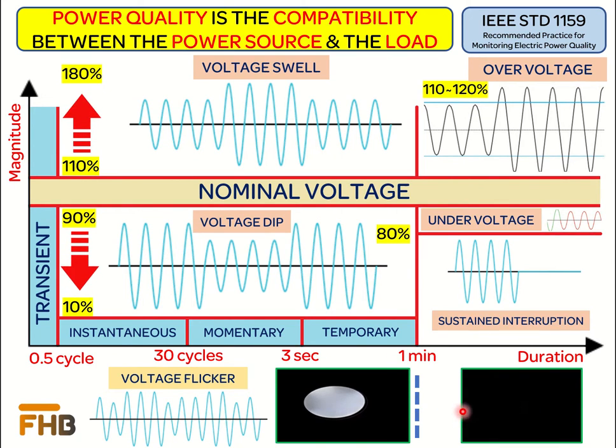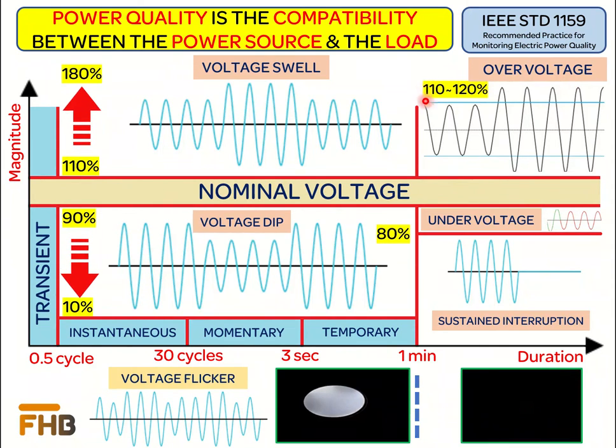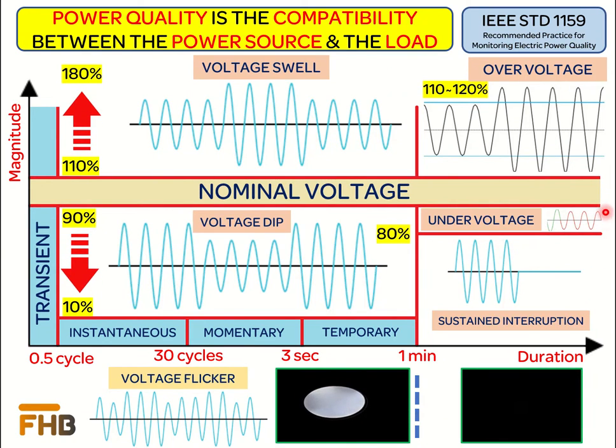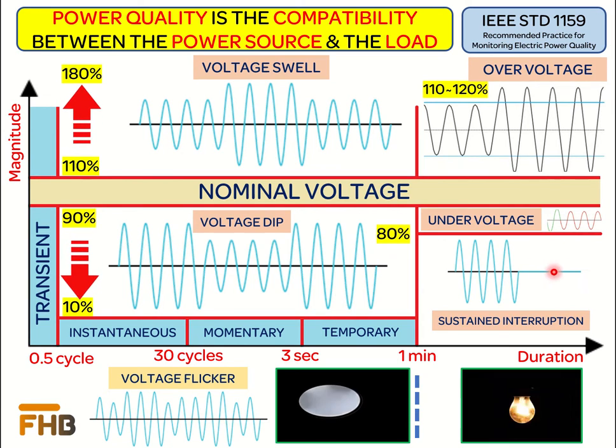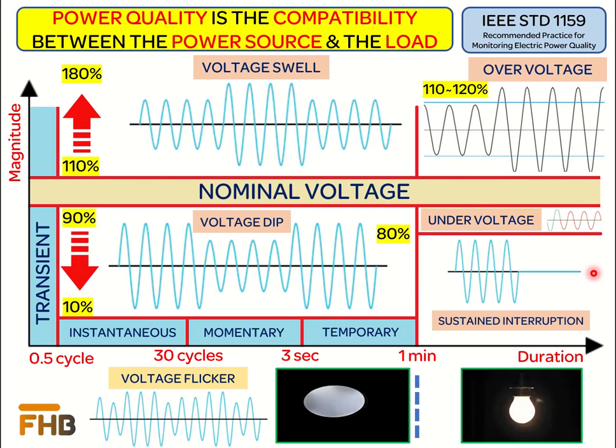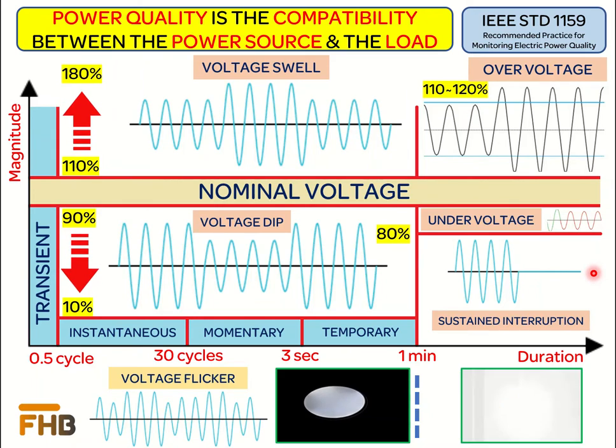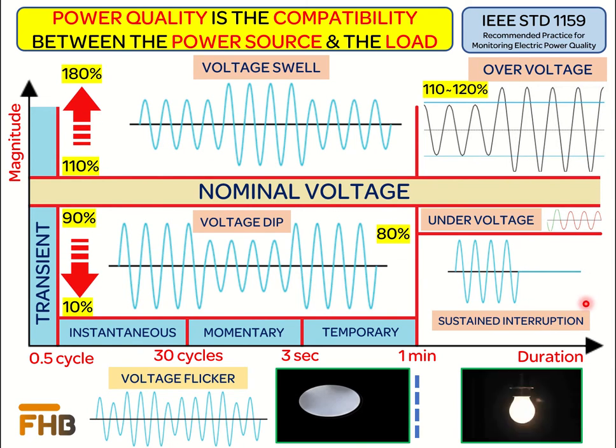Now we will discuss about the long duration variations. Overvoltage is a long duration variation which lasts more than 1 minute and has a magnitude of 110 to 120% of the nominal voltage. Undervoltage is a long duration variation which lasts more than 1 minute and has a magnitude of 80 to 90% of the nominal voltage. An interruption is a complete loss of voltage, or the magnitude of the supply voltage drops below 10% of the nominal voltage. If the interruption is less than 1 minute, then it is considered as a momentary or temporary interruption. However, if the interruption lasts more than 1 minute, then it will be considered as a sustained interruption.